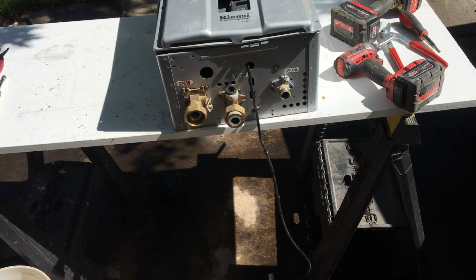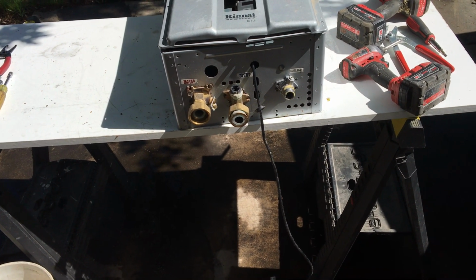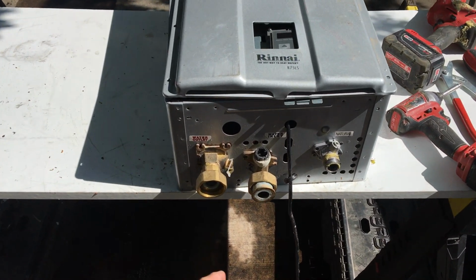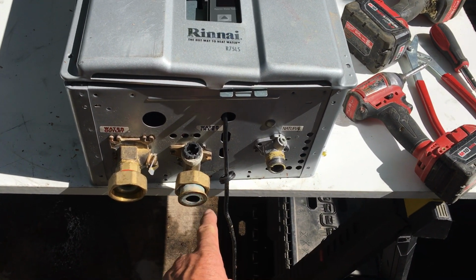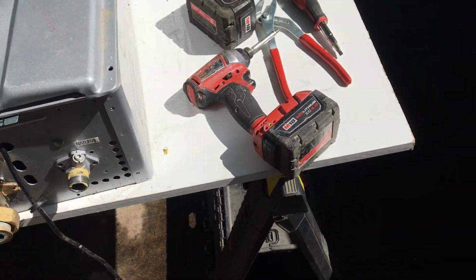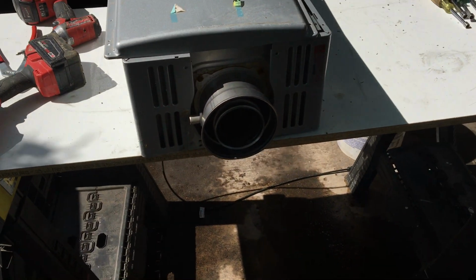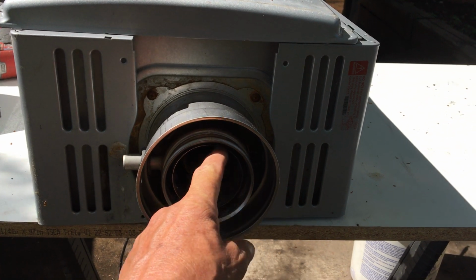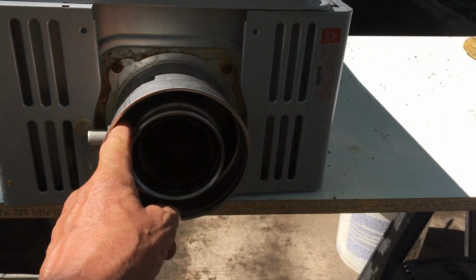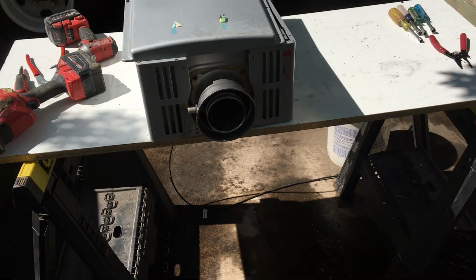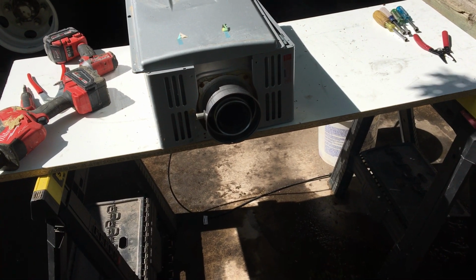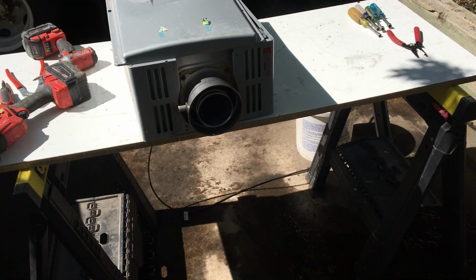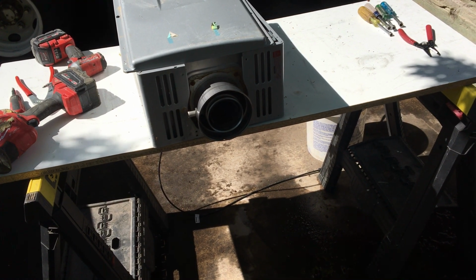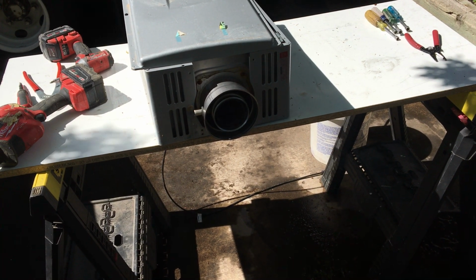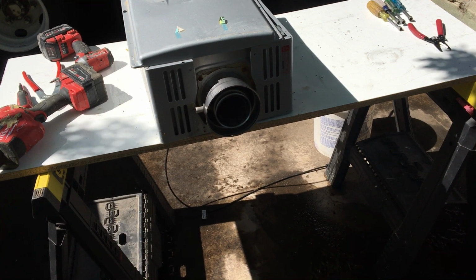This is a 200,000 BTU water heater. Water outlet here, water inlet here, gas input there. Around the top is the flue, which comes out here in the center - that's the exhaust. The air is brought in around, and if I'm not mistaken, at least this model requires a proprietary venting system, a concentric vent type of venting system, which is another reason I never really cared for them. I like to make my own vents.